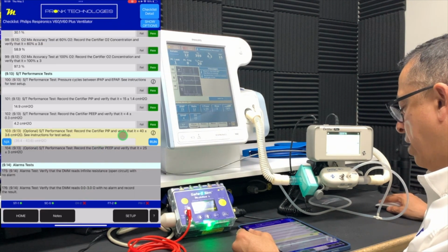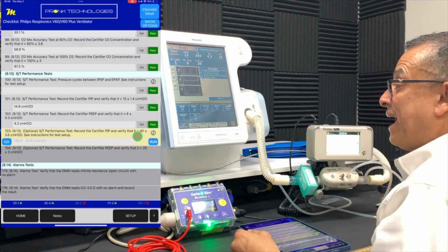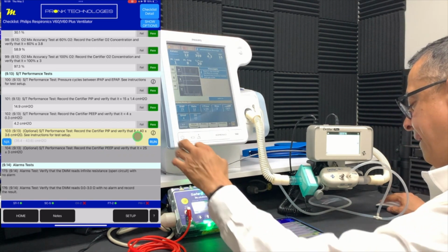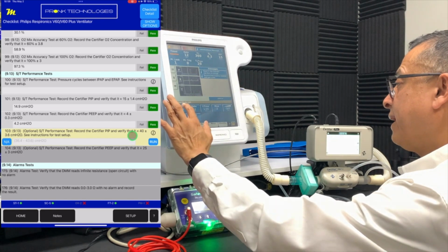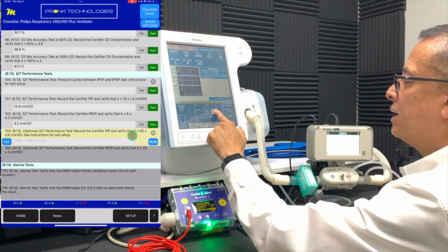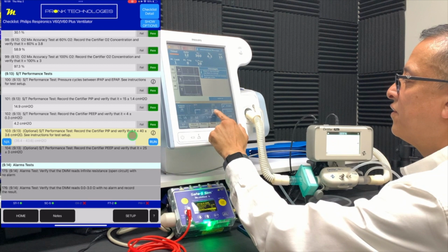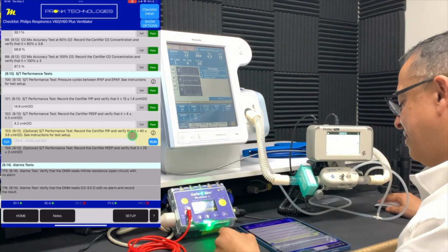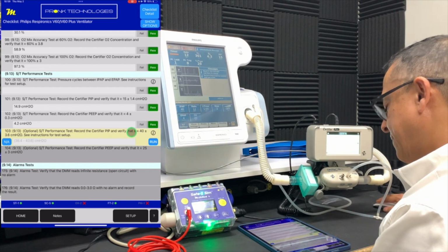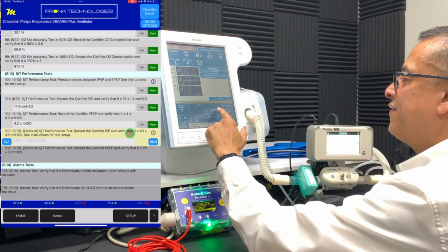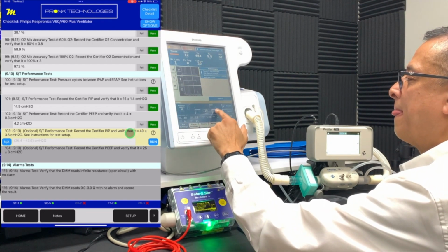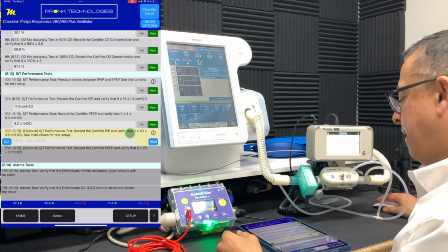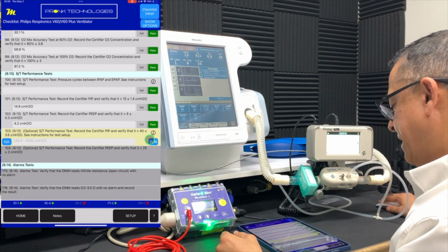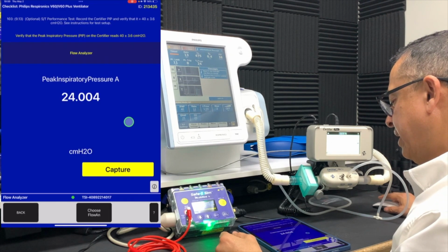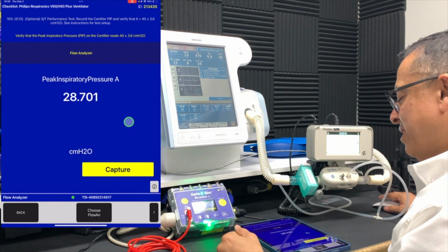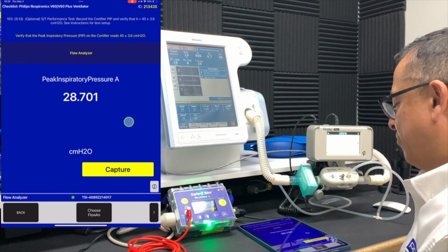Next, we now want to program it for an IPAP of 40. And so we're going to go ahead and do that. And we'll go ahead and set that up now. So we're going to increase this to 40. And we're going to set the EPAP to 25. And we're going to confirm that the PIP value is 40. So we'll wait a moment here for it to reach that peak pressure.